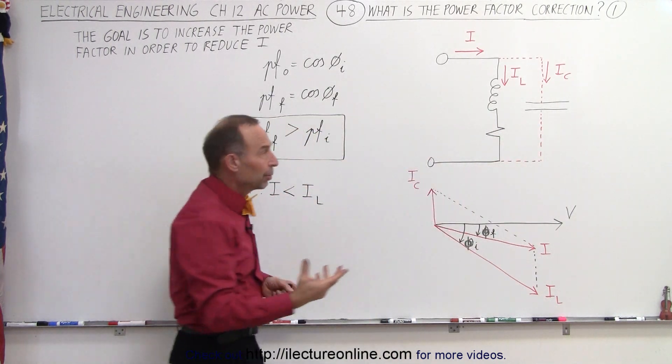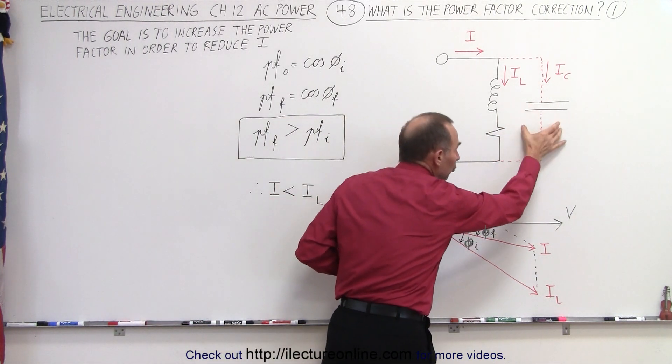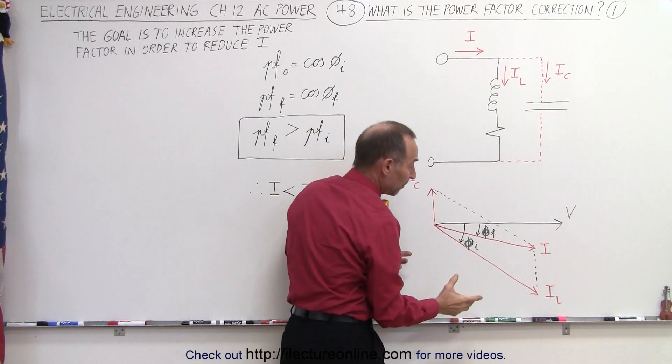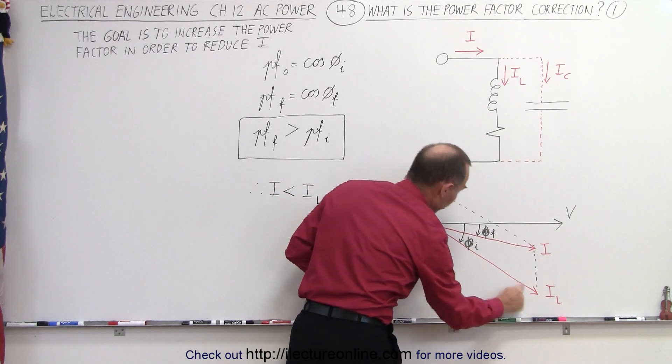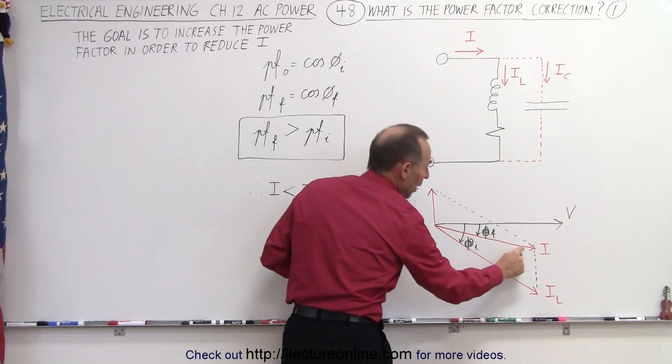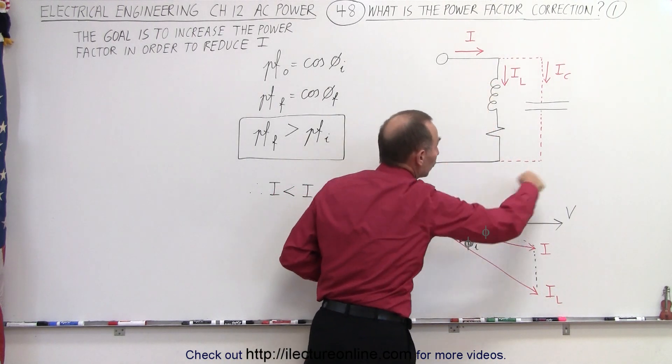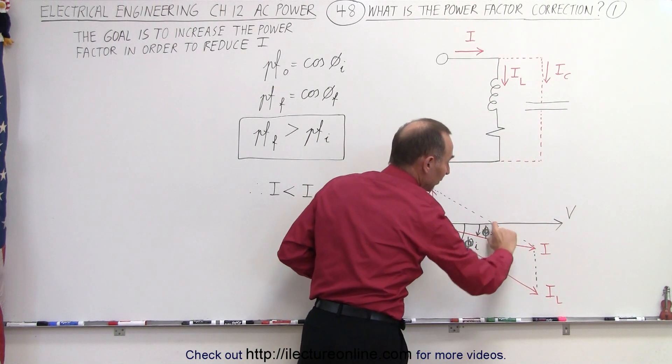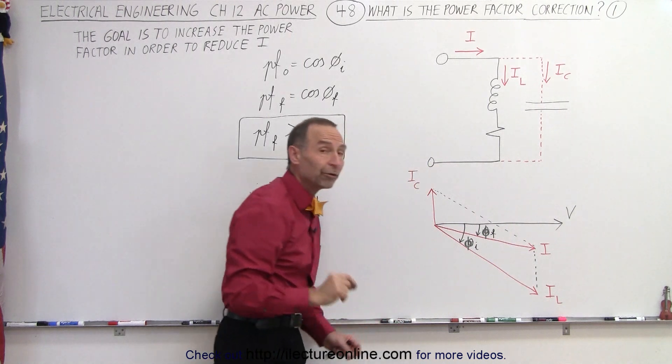Therefore, actually putting a capacitor there reduces the current requirement. You can see how that works here by doing a vector sum. If we add the load current to the capacitor current, we now have the current provided to the whole component. And that current is now going to be less because we now have a smaller phase angle.